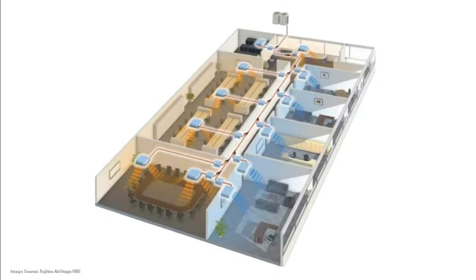And if you look at the units which are able to recover heat, this will actually be able to take heat from the indoor cassettes which are calling for cooling, and it will take that unwanted heat and move it to any cassette internally which is calling for heating. So this means that heat is not having to be generated within the building, and that also means the compressor has to do less work because it's not trying to reject any heat or less heat, and it's pushing that instead over to the indoor units which are calling for heating. So as we saw slightly earlier, each zone can be individually controlled, and if one cassette breaks, then the rest of the system can continue to run unaffected.